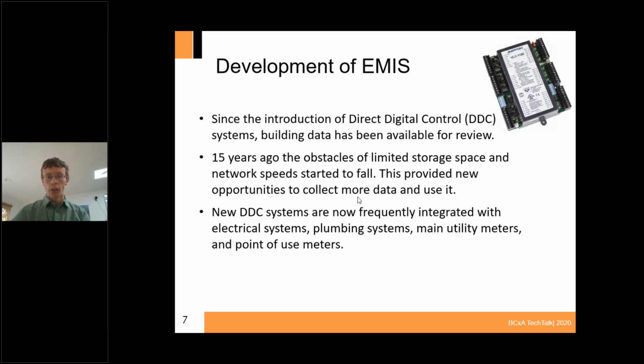Note that we're also now integrating our HVAC system controls into the electrical systems, in particular the lighting controls. We also pick up meters on the electrical panels if they're installed that way. For plumbing systems, maybe there's not so much information to be gathered, but we are picking up temperatures and status points on the water heaters and pumps. We're obviously picking up the main utility meters, and if we're lucky, we can get point-of-use meters throughout the building. Depending on your codes, the IECC is now requiring sub-metering of all the different systems, and I think we're going to see a lot more of that.